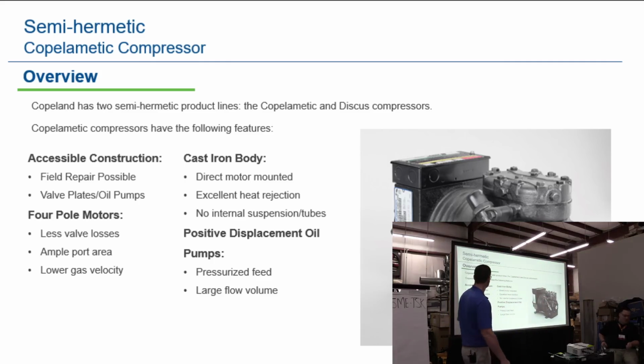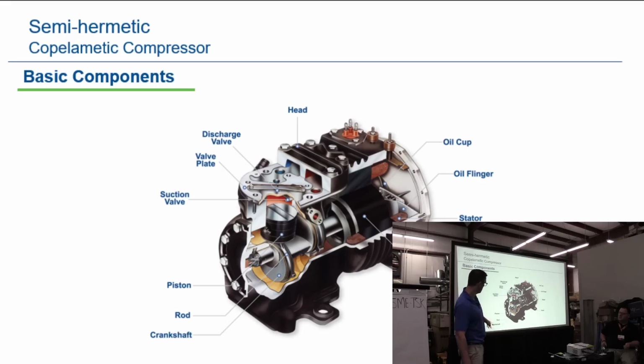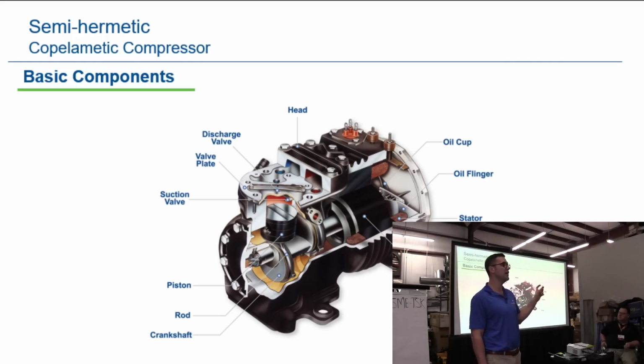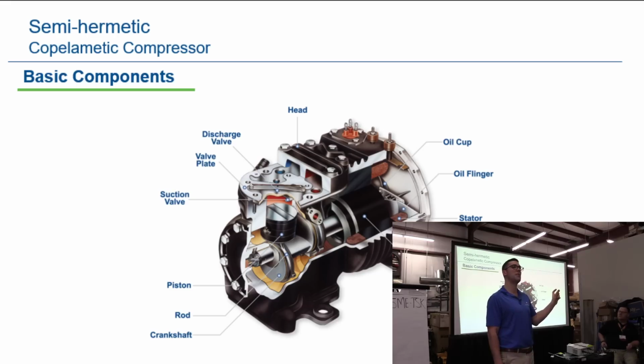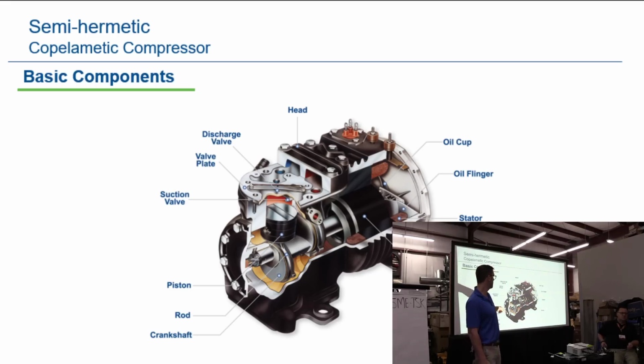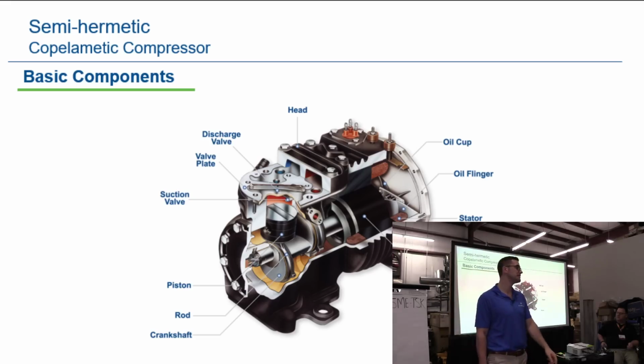Okay? Field repair is possible, valve plates, oil pumps, depending on the model. Let's get into it. So, crankshaft, rods, piston, suction valve plates, discharge valve, heads, oil cup and flinger, depending on the model. And you'll find all this information in the model number of the compressor. You go to Copeland Mobile and it'll tell you what's in there. Is it a pump model or is it a flinger model?